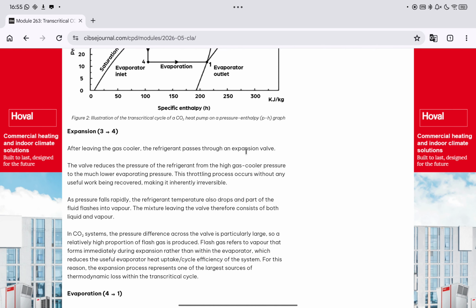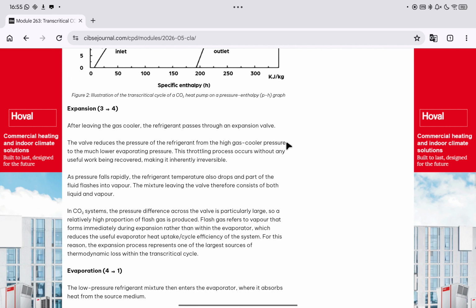Expansion. After leaving the gas cooler, the refrigerant passes through an expansion valve. The valve reduces the pressure of the refrigerant from the high gas cooler pressure to the much lower evaporating pressure. This throttling process occurs without any useful work being recovered, making it inherently irreversible. As pressure falls rapidly, the refrigerant temperature also drops and part of the fluid flashes into vapor. The mixture leaving the valve therefore consists of both liquid and vapor.